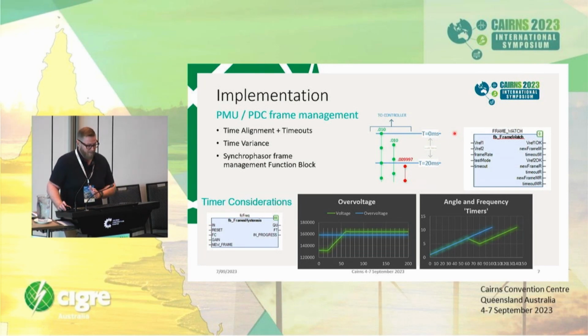So what we went with then was that rather than potentially operate early or unnecessarily, we just count the frames. So anywhere where, if we've been told to use a 200 millisecond timer for phase angle difference, if we downsample to 100 frames per second for the synchrophasors, we're counting 21 frames. We're not counting 200 milliseconds, we're counting the frames.